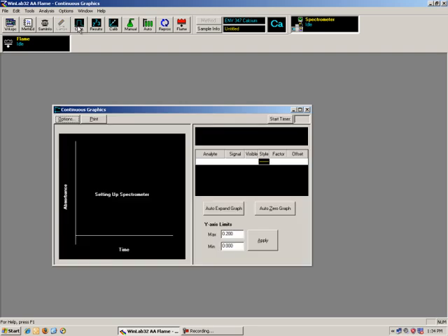Now this will actually show the absorbance reading using the beam that's not the reference beam, but a sample beam that will go through the flame. And you can see right now it's set at about 0.024, and it's fairly constant. That's a very low absorbance level.